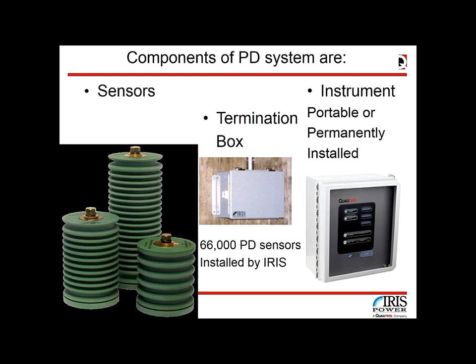To start monitoring, sensors must be installed. Sensors come in different shapes and sizes, but it is important they are designed specifically for PD data collection — multi-purpose sensors do not do an excellent job. Purpose-designed PD sensors are better than general-purpose alternatives. Once permanently installed inside the machine, there will be a connection termination box between sensor and instrument, which can be portable or permanently installed.